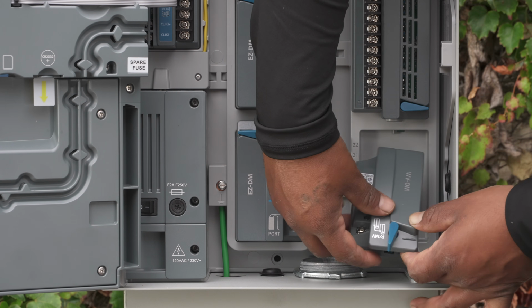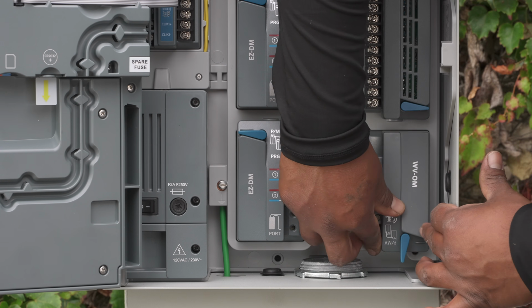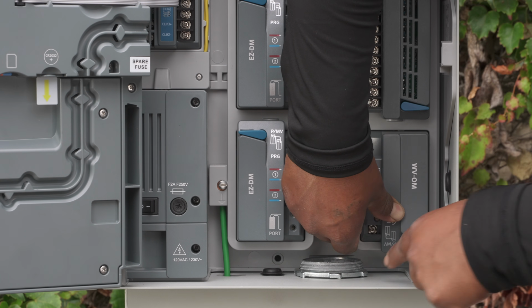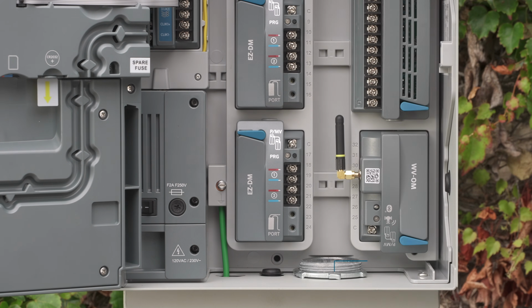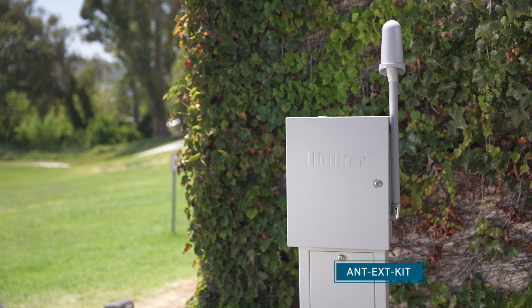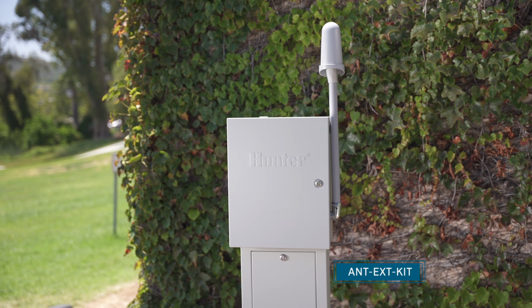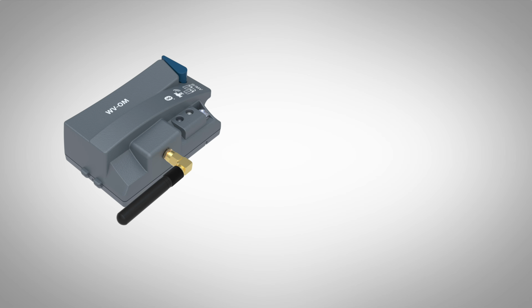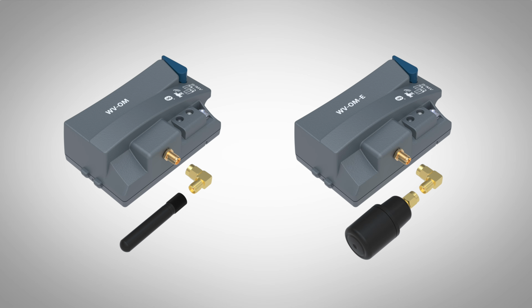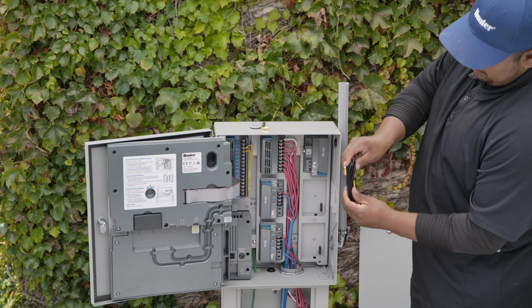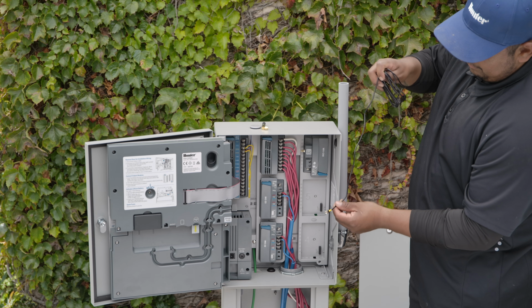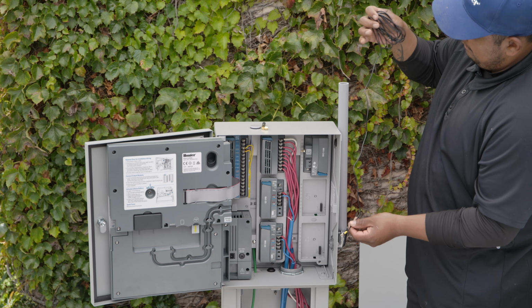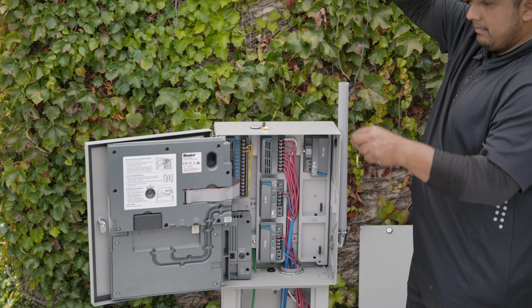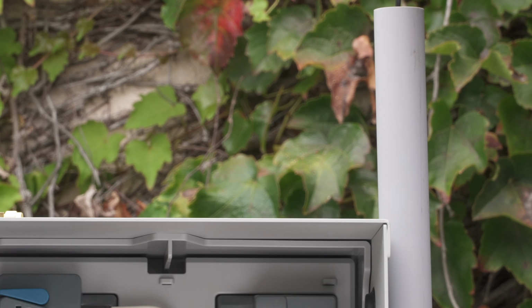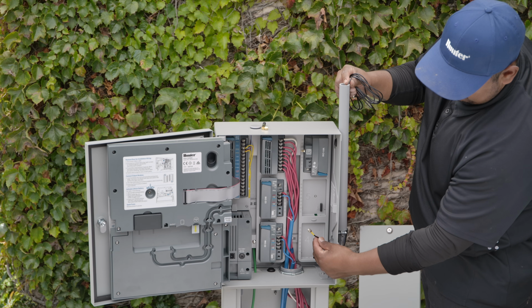WVOM wireless output modules do not have field wiring. Instead, you'll connect an antenna, preferably to the external antenna extension kit, ANT-EXT kit, outside the controller enclosure. To install the antenna, remove the existing antenna from the wireless valve output module. Thread the male end of the extension cable to the wireless valve output module. Route the cable out of the cabinet to the desired mounting location.